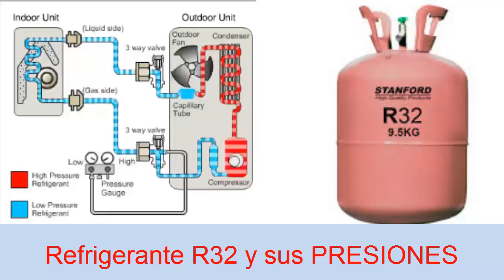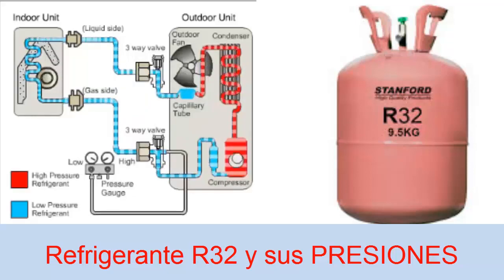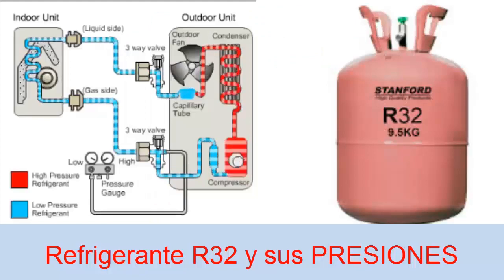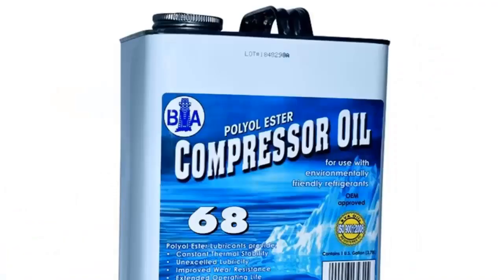Here we have to understand something. As the R32 is a pure refrigerant, it can be charged in both liquid and gaseous phases. With respect to oil, R32 units usually work with a slightly lower viscosity than R410A, although this is a general guideline — we must pay attention to the viscosity the compressor manufacturer stipulates for that specific model. However, on average, those viscosities generally do not exceed 68.